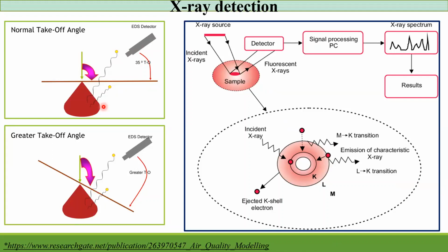It's making the sample tilted towards the detector, but at the same time, you need to keep in mind the electron should come and hit the sample. Then only the X-ray will be emitted. So you need to balance those tilting angles to get as many electrons as possible to the specific region and towards the EDS detector. But in SEM, mostly we are not using much tilting. Of course, we need to tilt when it is required, but in most SEM cases, we just take without tilting.